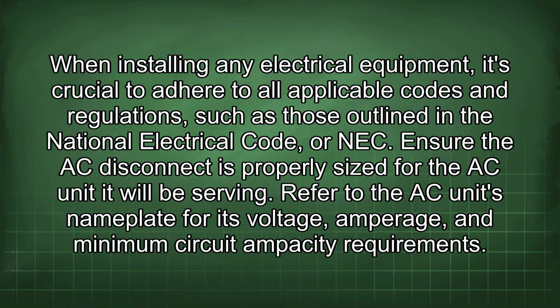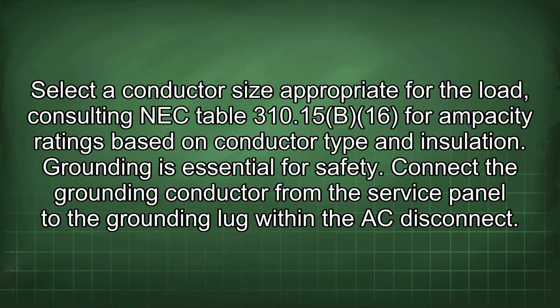Ensure the AC disconnect is properly sized for the AC unit it will be serving. Refer to the AC unit's nameplate for its voltage, amperage, and minimum circuit ampacity requirements. Select a conductor size appropriate for the load, consulting NEC Table 310.15(B)(16) for ampacity ratings based on conductor type and insulation.